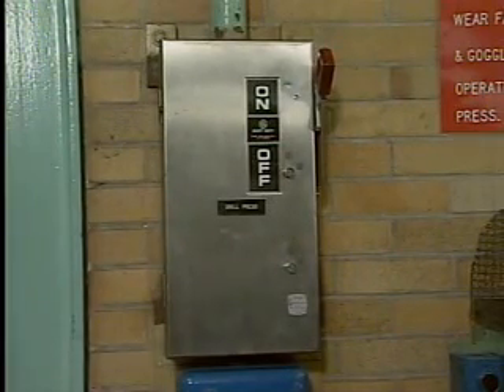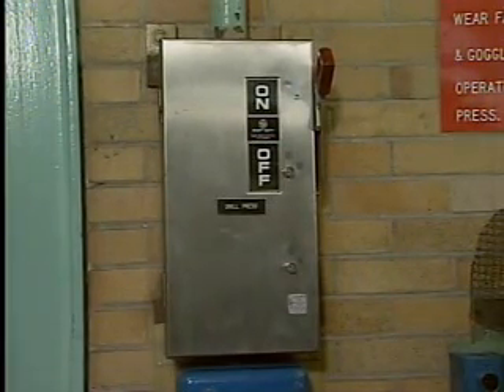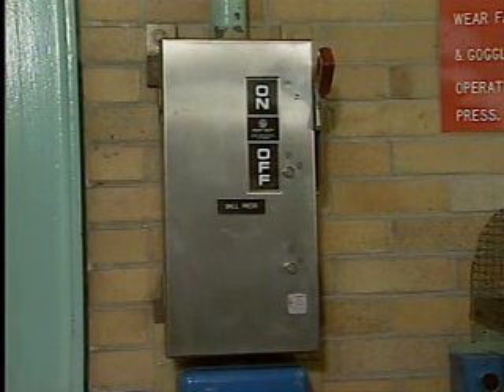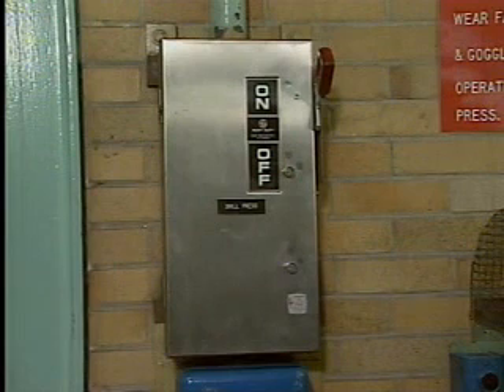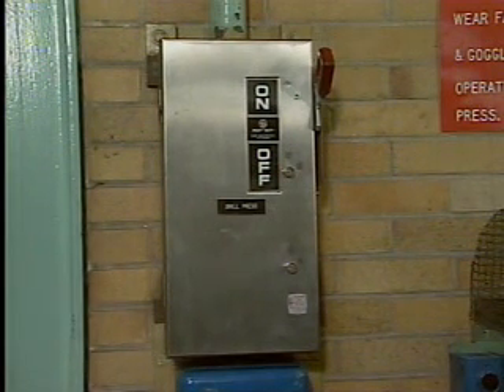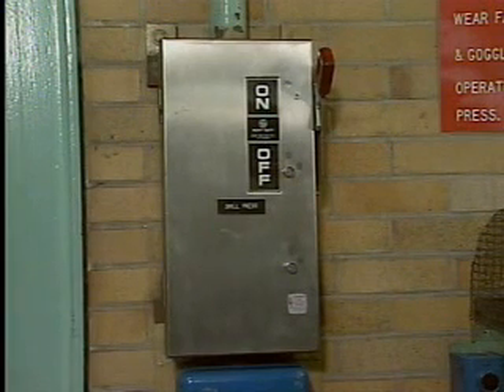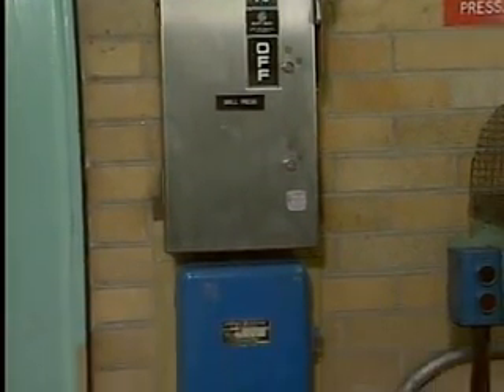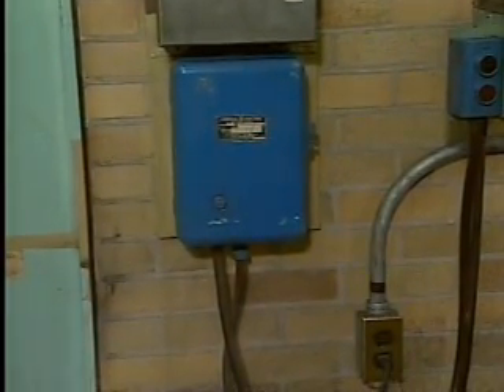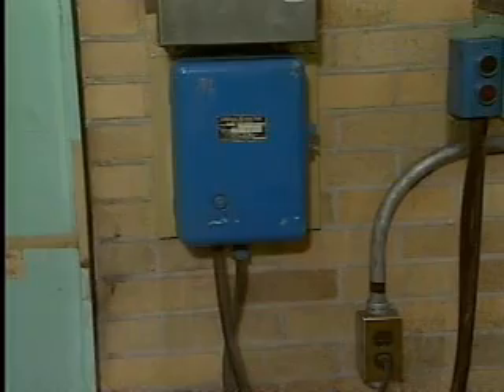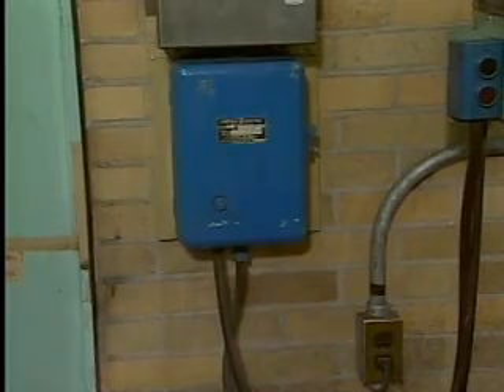This circuit's operating voltage is applied to the fuse box, so that would be a logical place to make this check. However, this fuse box has a safety interlock that does not allow the fuse box to be energized while the door is open, and the electrician can't take voltage measurements inside the fuse box while the door is closed. To check the circuit's operating voltage, the electrician decides to measure the voltage at the point where the power lines from the fuse box enter the control cabinet.